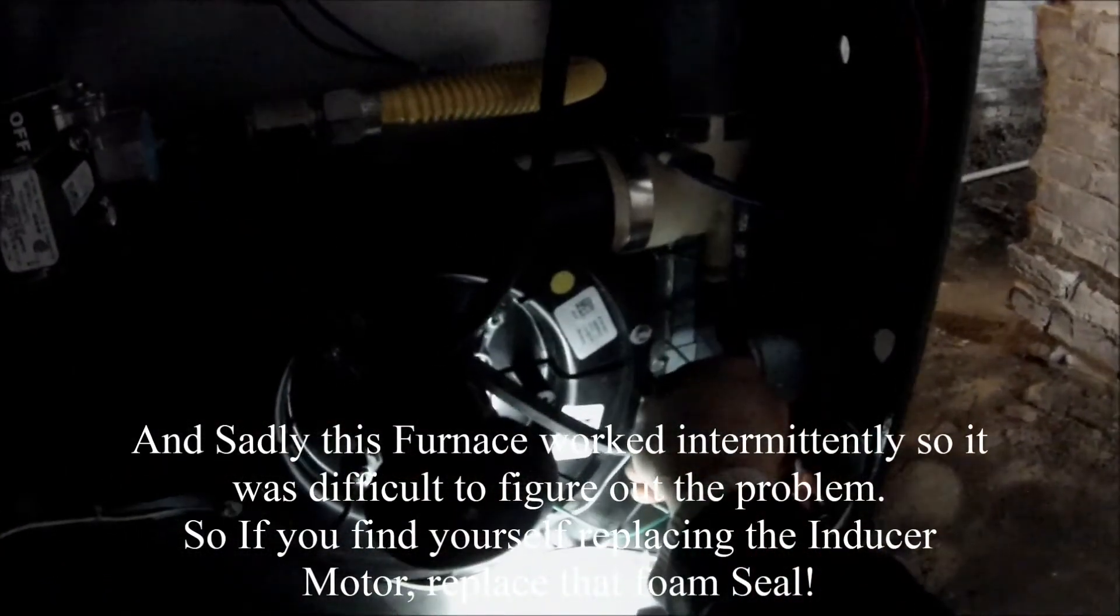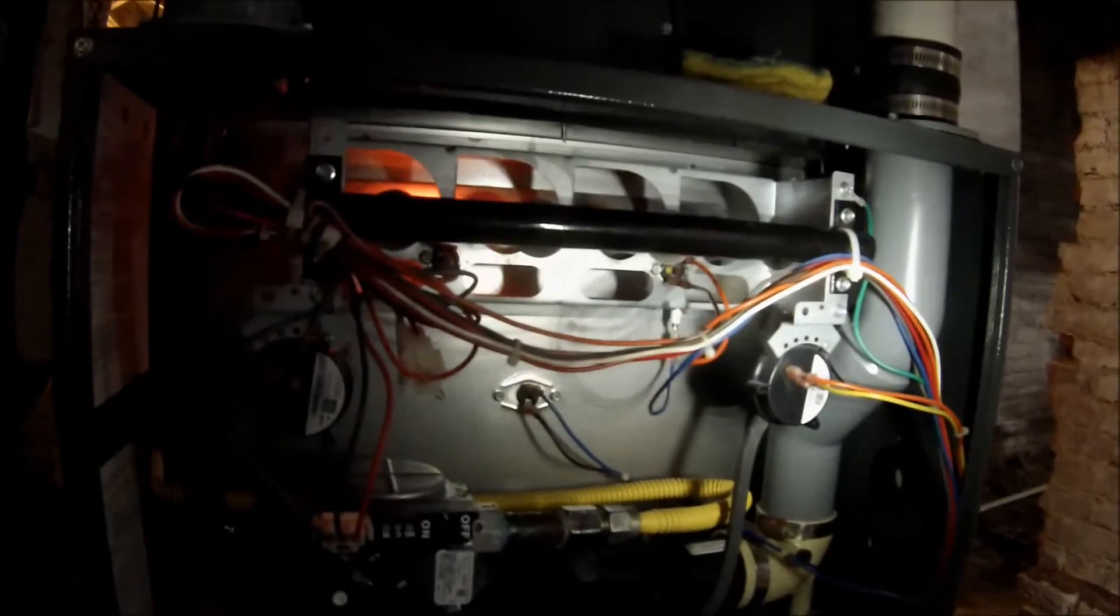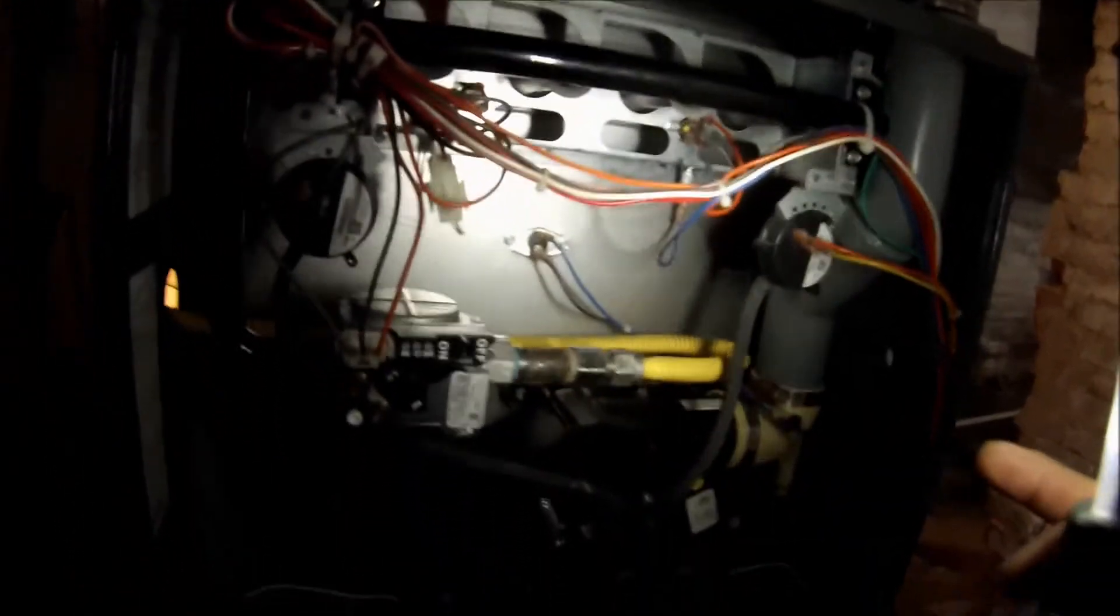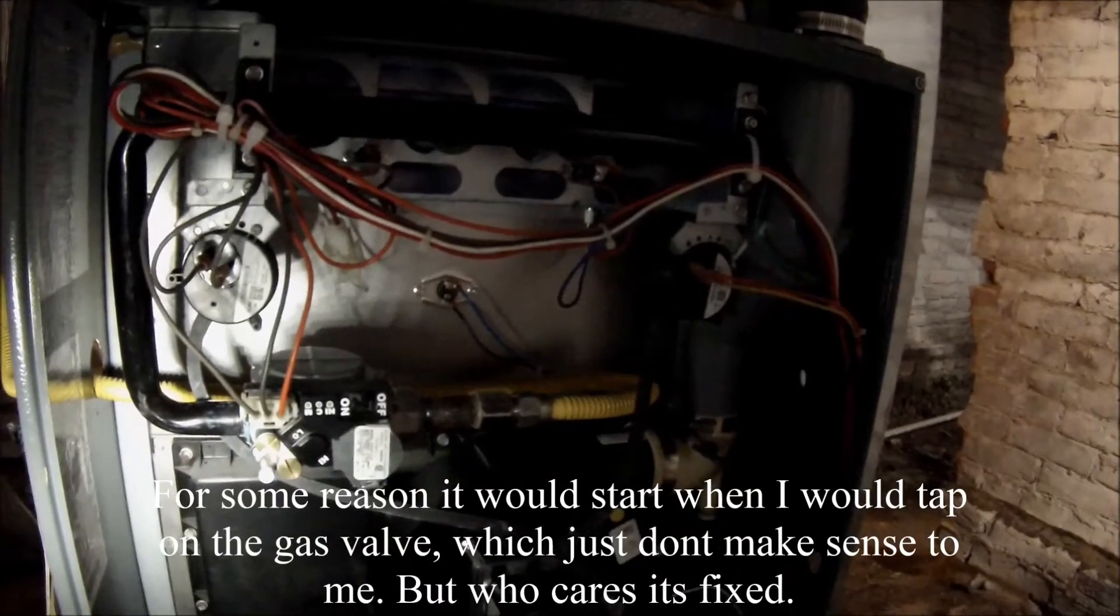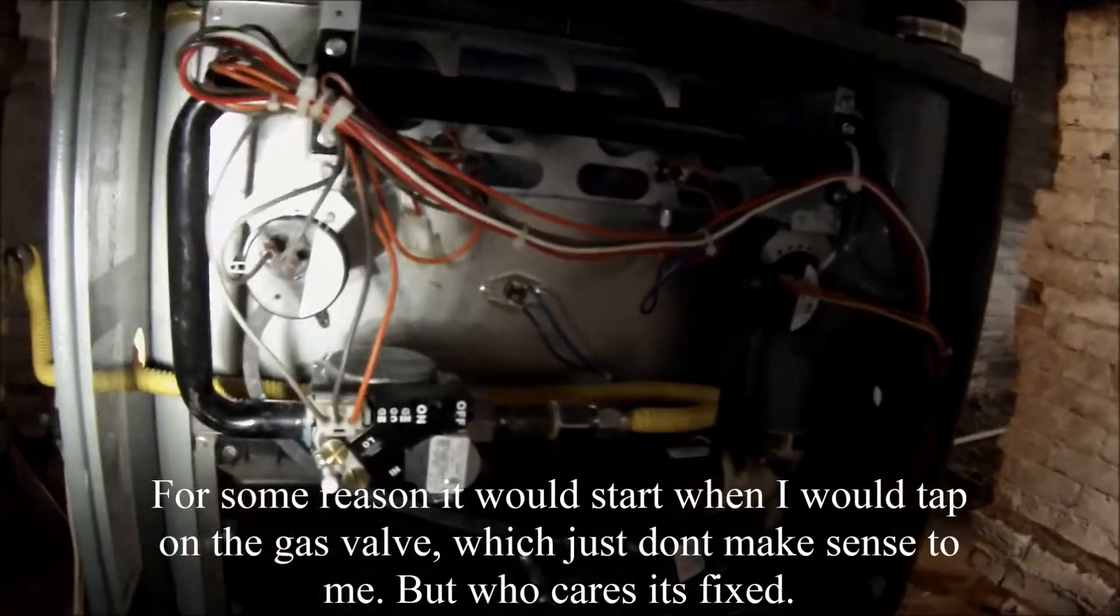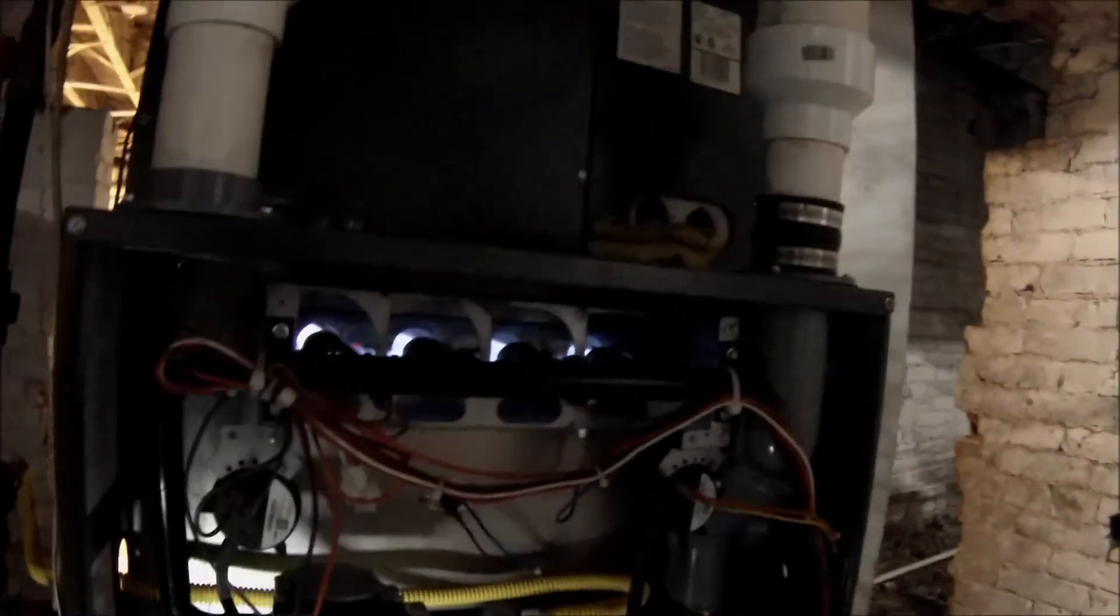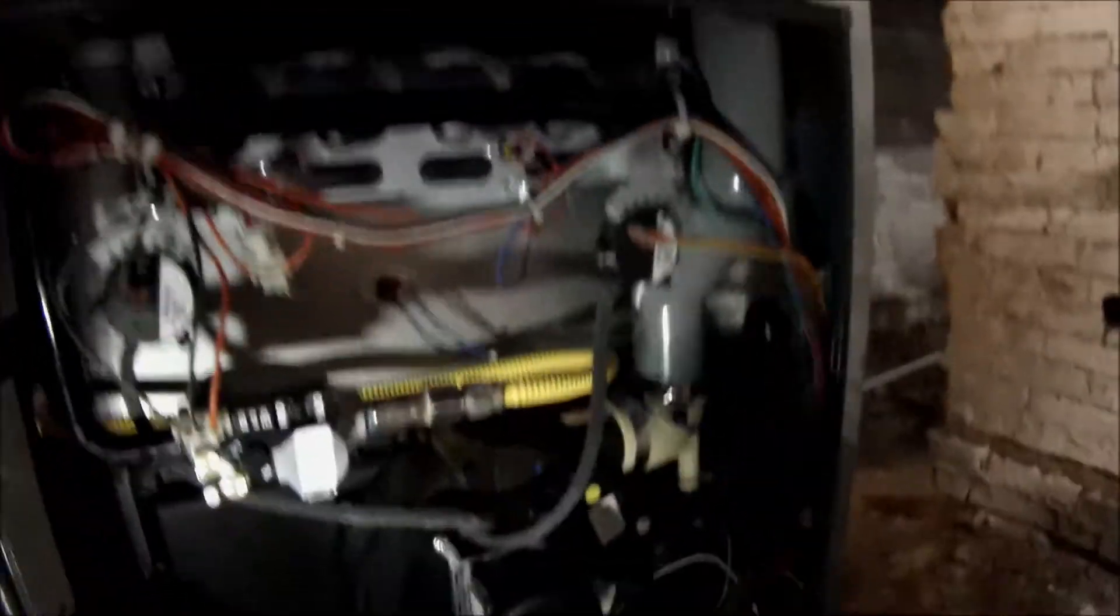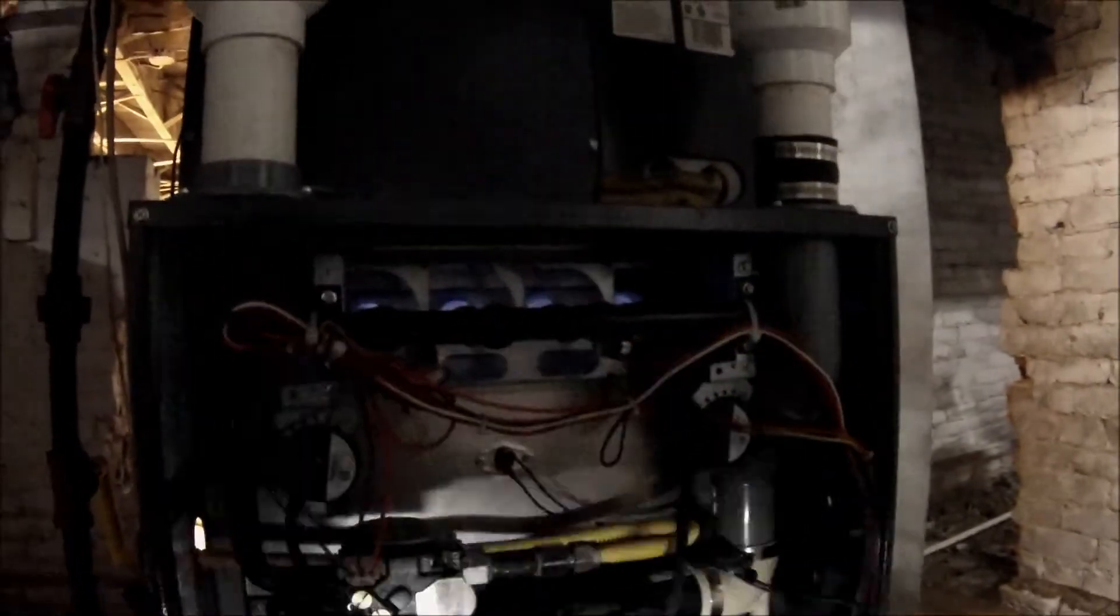But again, that seal was probably causing the air to not have that negative air that it needs to suck from this hose here. Because if you take this hose off, see you got no flame. You got to have that negative pressure pulling from the inducer from this little containing box right here. And that's, it's a double pressure switch. So it's got one in the front side and it's got one down there. Right here. So if either of those ones are not getting, if they're not working, this thing won't work. And it's sad because I was thinking it was the valve the whole time because I didn't have any fault codes for these pressure switches. And it would work sometimes and sometimes it wouldn't. So, but we'll see. I'll keep you updated and let you know if this is 100% a fix. But I'm pretty sure that was, was it. It's just that seal was not allowing it to keep suction, but we'll see.